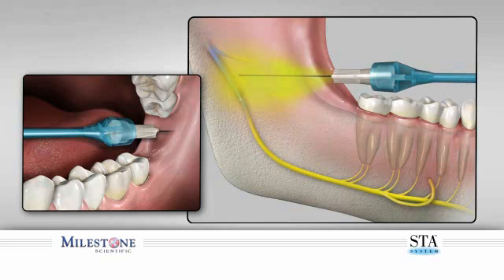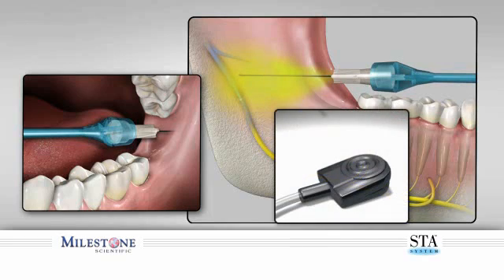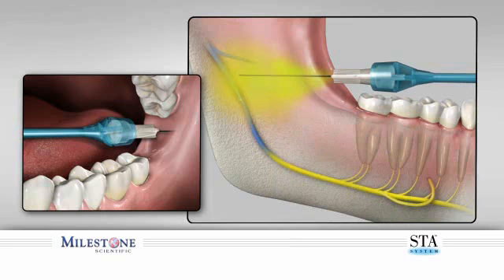Once at your target site, perform an aspiration by depressing and releasing the foot control. If the aspiration is negative, continue the injection. If aspiration is positive, reposition the needle and repeat aspiration by depressing and releasing the foot control pedal again until a negative aspiration is obtained.